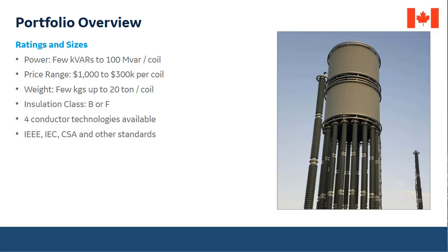And if I can recommend something to the users or to the ones that are specifying the reactors: insulation is one of the most, if not the most, important materials that goes inside of a reactor. So if you want to know if you're buying a good product, ask about the insulation. Ask about the quality, the supplier, the origin, because that's basically what's going to drive the design and confirm that it's going to last for 30 years and more. Again, I'm not going to mention what GE is doing, but this is very important: the insulation material that you use, that we use in this case. There are different types of conductive materials: aluminum profiles, single wires, stranded cables, flat transposed, and continuous transposed cables.